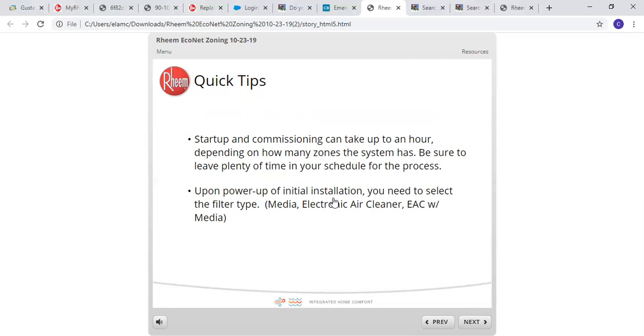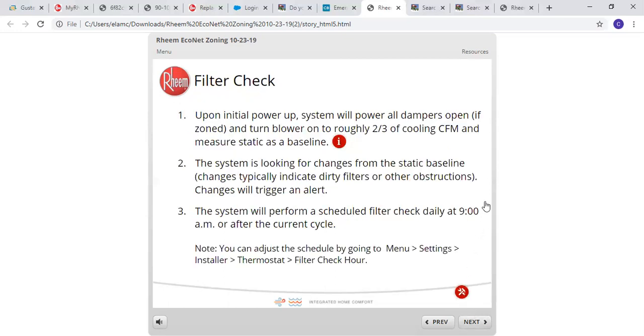Upon power up of the initial installation, you need to select the filter type. Are you using a media, electronic air cleaner, or an EAC with media? The filter check: upon initial power up, the system will power open all dampers if it's zoned and turn the blower up to roughly 2/3 of cooling CFM and measure static as a baseline. The system is looking for changes from the static baseline. Changes typically include dirty filters or other obstructions, people shutting registers, blocking returns, you name it. Any changes from this will trigger an alert.